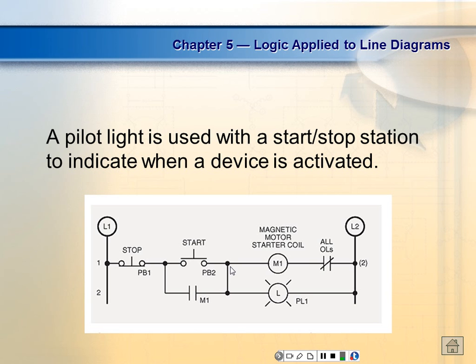So this one would indicate if there should be power to the coil. What this is telling you is, if this light comes on, there's a 99% chance that that coil right there has got power to it. And the only thing that would cause you a problem is the overload. So these indicator lights can't tell you when something is running. All they can tell you is when something's got power, right? Y'all understand that? Hooking them in parallel, in series, or by themselves would indicate this guy is not energized. But if it comes on and this is not energized, then there's a high probability it's either your overload or the coil itself, right? And you can find that in a heartbeat with a meter.